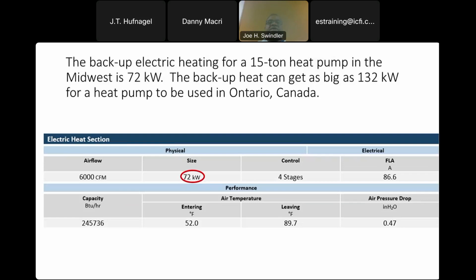So just a typical example, just to give you a better idea of how much backup electric heat is needed. For a 15-ton heat pump in the Midwest, 72 kilowatts of electric backup heat is needed. And if you go up to Ontario, Canada, which we have a plant in Canada, where it gets much colder, you can need as much as 132 kilowatts of backup heat. And again, the problem with that is bringing that power to the heat pump as backup heat. So that's all that electric equipment.